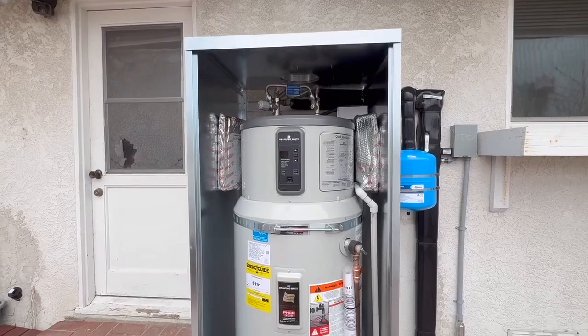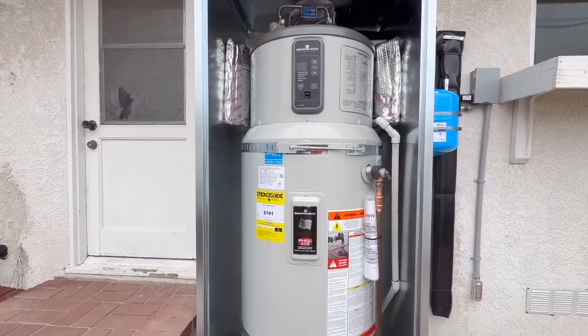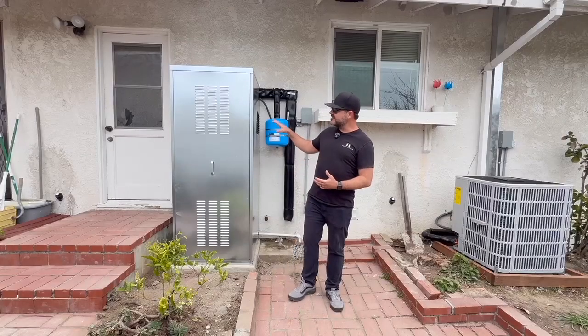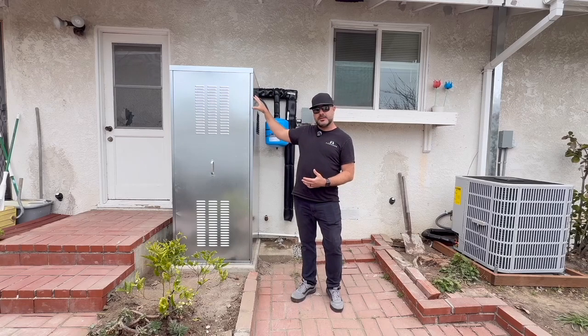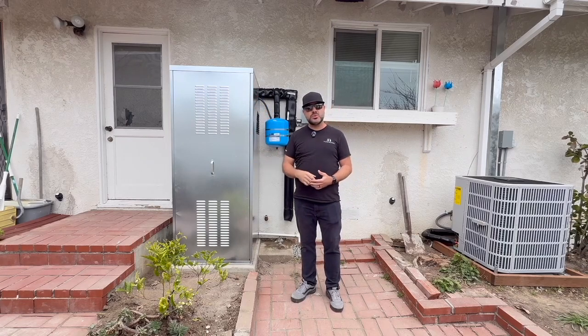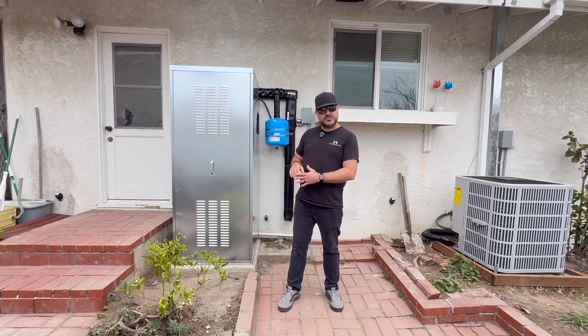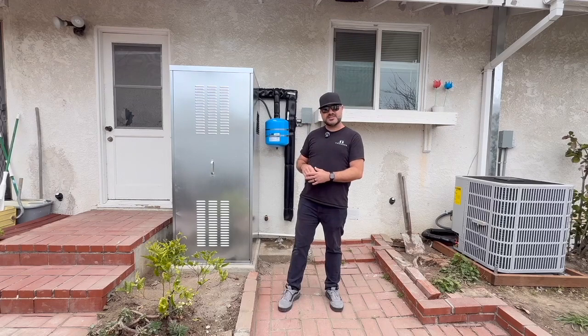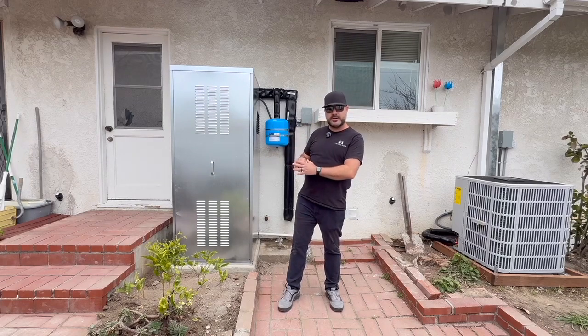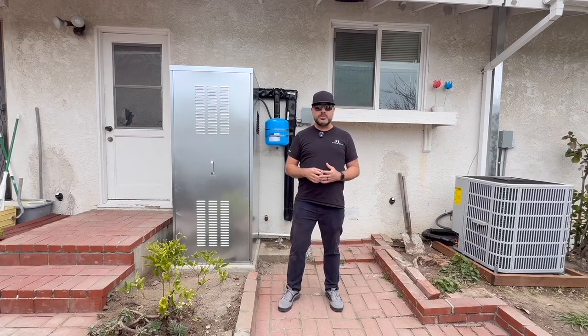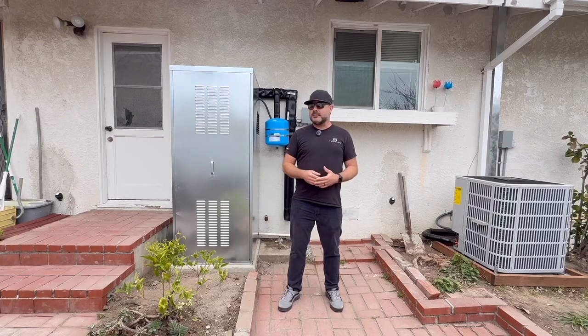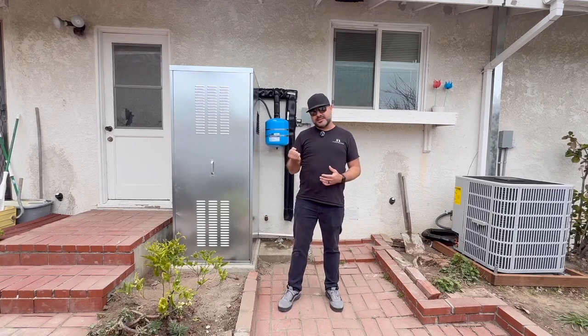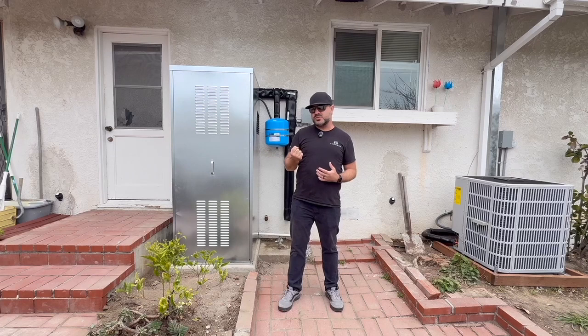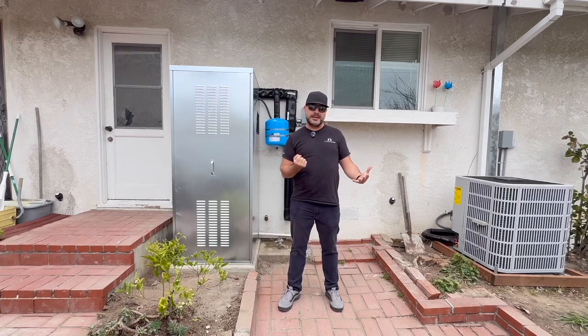This is not just a heat pump water heater, it's a hybrid heat pump water heater. It has the heat pump on top of the tank, but also in the tank are two resistive electric heating elements, just like an electric tanked water heater has. The uniform energy factor, or coefficient of performance, of this tanked hybrid heat pump water heater is somewhere around 3.7 to 3.9, meaning every unit of electricity consumed actually produces 3.7 to 3.9 units of heat.